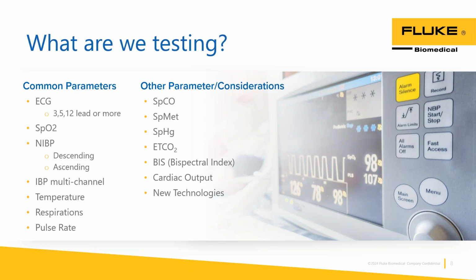SpO2, do we have the right SpO2 cable on it? Some are interchangeable, some are not. Is it non-invasive blood pressure? Does your monitor have ascending non-invasive blood pressure or descending non-invasive blood pressure? Because this can change how you get your readings. And of course, we always know that when we're going to do non-invasive blood pressure, we should check that through a static pressure, not a dynamic one, because with dynamic, bleed down rates are going to affect it, the cuff's going to affect it, and what's the chance, even at 60 beats a minute, of hitting the 120 mark right on the money? So we always want to do those checks at a static pressure and then just do verification that it's reading right and check your alarm limits with a dynamic pressure.